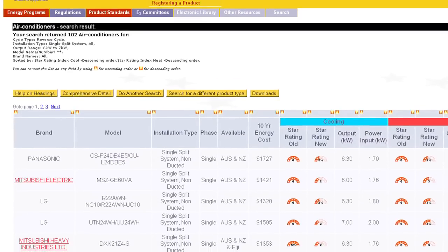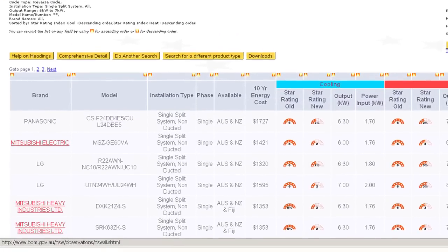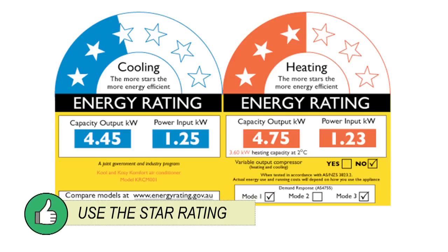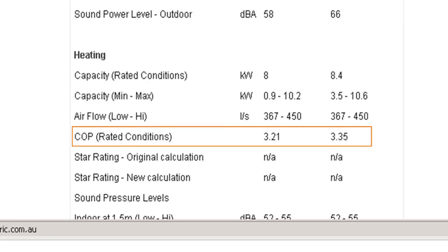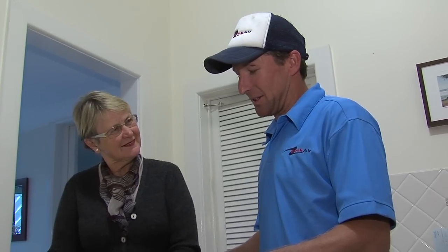Once you've worked out your client's load requirements, choose the most efficient system to service that load. Use the energy star rating to help. Multi-head and ducted systems usually don't have a star rating, so use the coefficient of performance and energy efficiency rating instead. Give the customer estimates on running costs of each system, so they know what to expect.